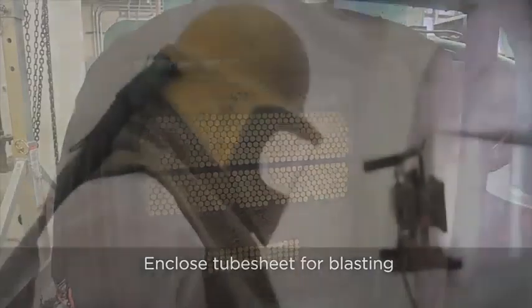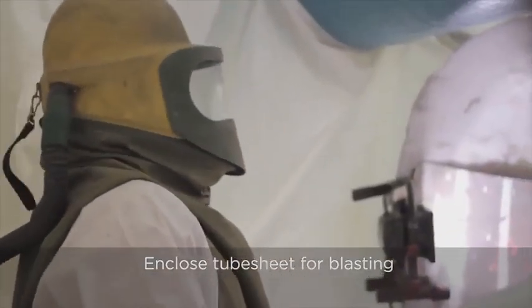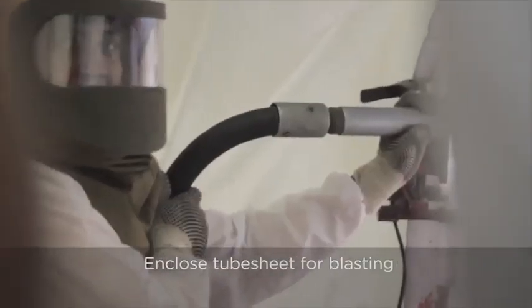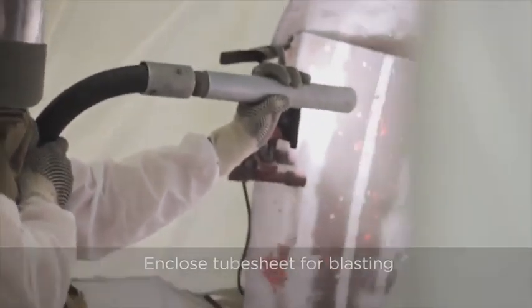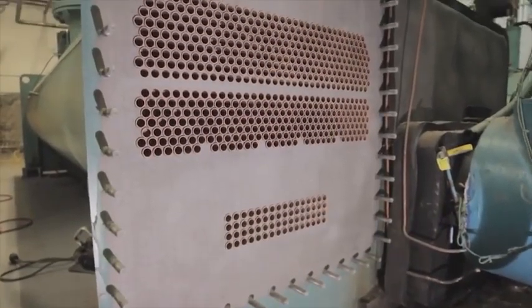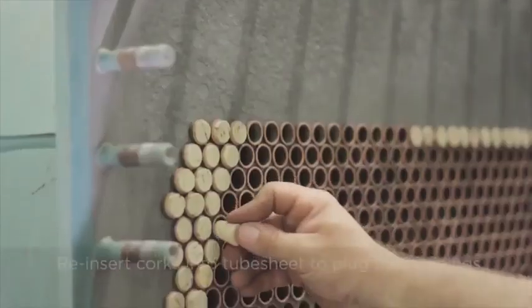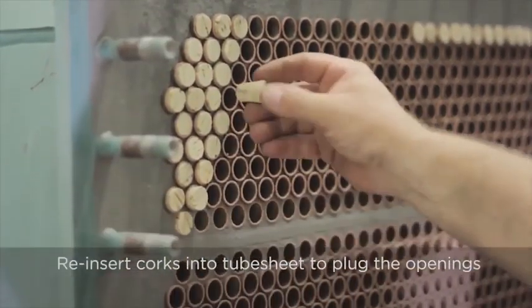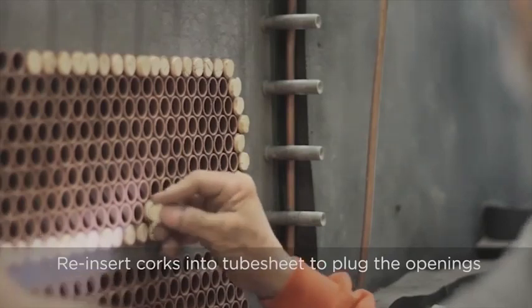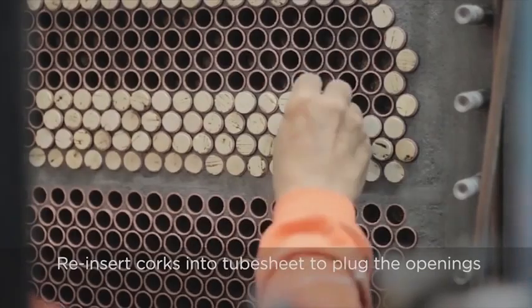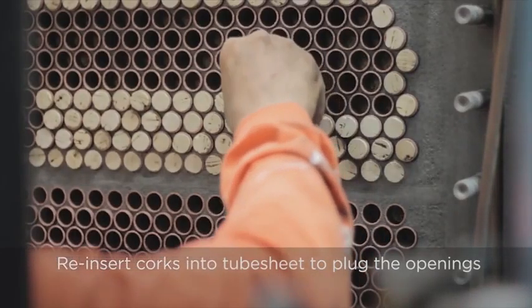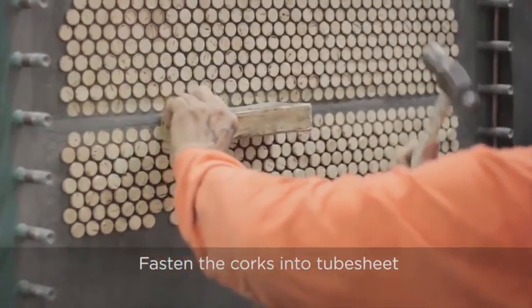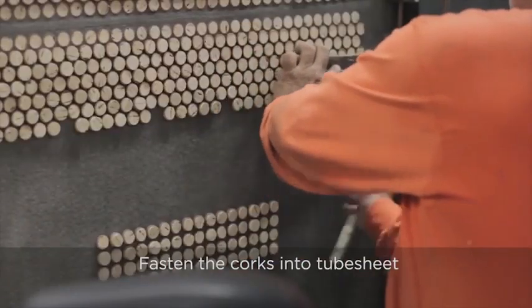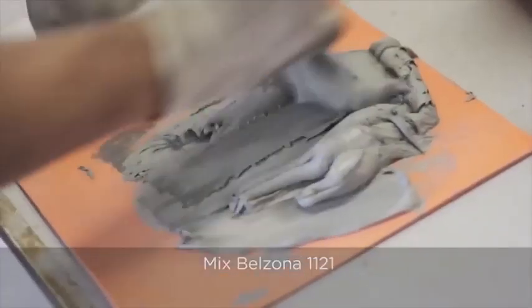So once all your corks are in and everything's enclosed off and ready for blasting, you start with surface preparation. Ideally, grit blasting is the preferred option because it removes all the corrosion and cleans the surface really well, and we're looking for a 75 micron profile to the surface. Afterwards, remove those corks and replace them because they would have been slightly damaged from the surface prep process, and refasten the corks back into the tube sheet itself.